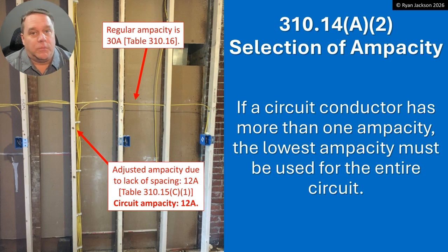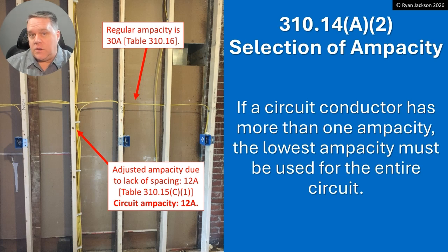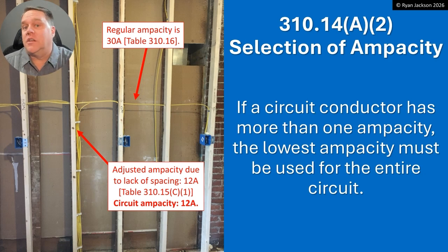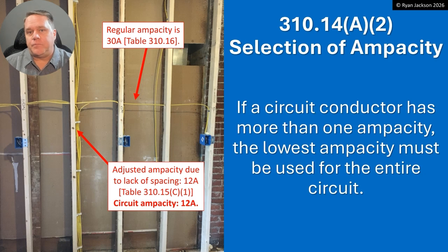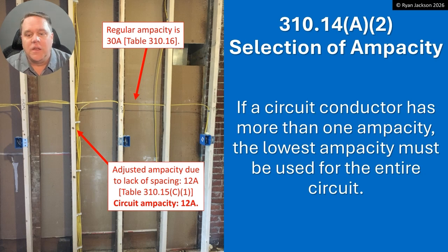If a circuit conductor has more than one ampacity, then the lowest ampacity must be used for the entire circuit. There's a lot to unpack here, and we're going to start with the definition of ampacity. Ampacity is a word that the code nerds made up — it's 'ampere capacity.' Only conductors have an ampacity; equipment doesn't. Equipment has ratings. The definition of ampacity is the amount of current that a conductor can carry continuously under the conditions of use without exceeding its temperature rating.